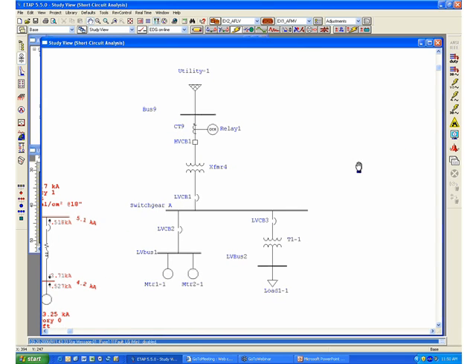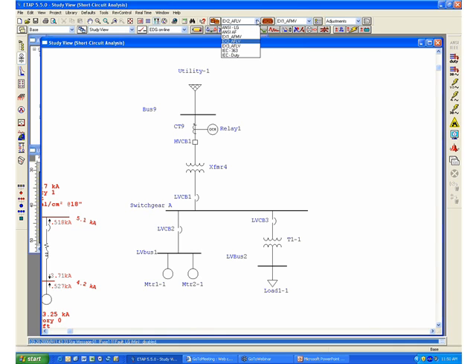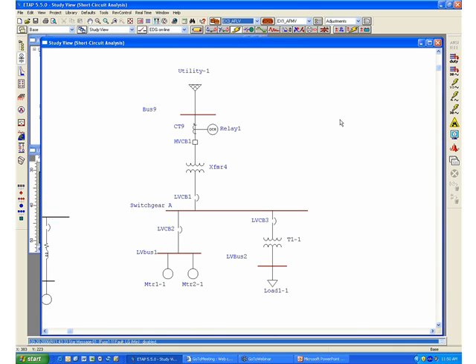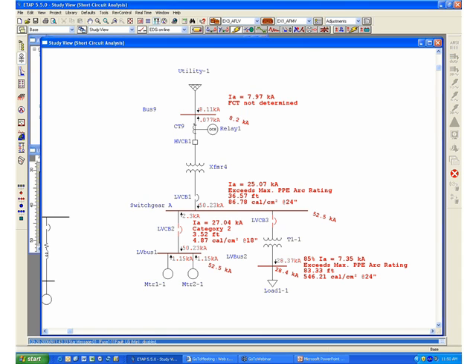This will show possible hazardous situations with the response of protective devices. In this case, I have a small system with a 480 volt system, and I'm going to perform an arc flash calculation on this system. The program comes up with some messages that we have not seen before.